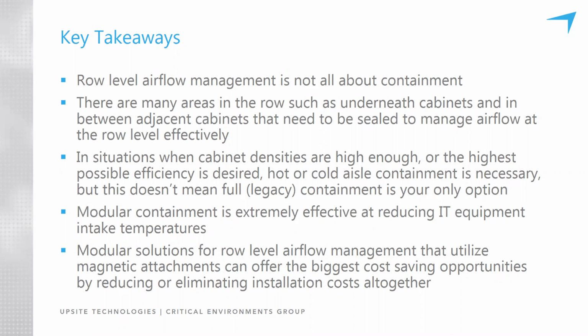When you need densities high enough that you need to scale and you're going to go full-blown containment, hot or cold aisle, that's where you're going to do the actual containment projects. But rest assured that those lower level investments need to be in place in order for a containment solution to be optimized and give you the ability to make the necessary changes.